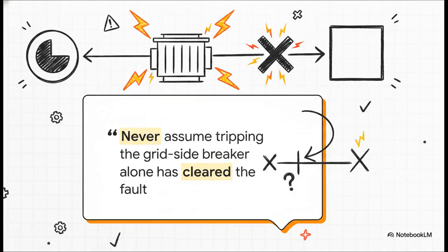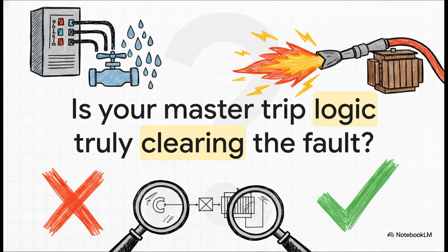Any protection scheme at this interface has to be designed assuming both sides can independently sustain the faults. So I'm going to leave you with this question to chew on as you review your own relay configurations. Is your master trip logic truly clearing the fault from all sources, or are you just shutting off the water main while the fire hose keeps pumping energy straight into your transformer core?